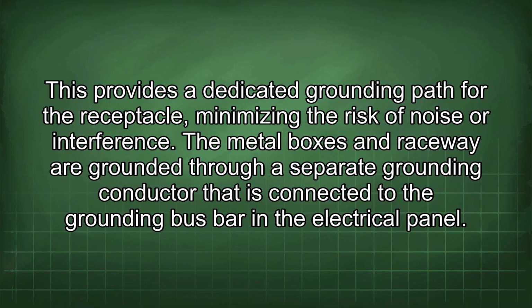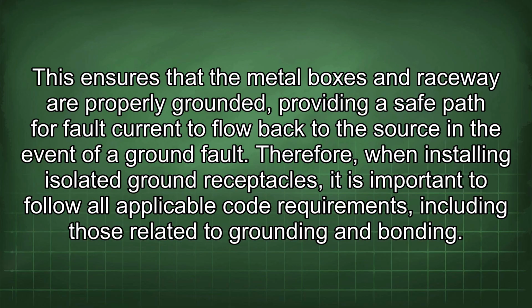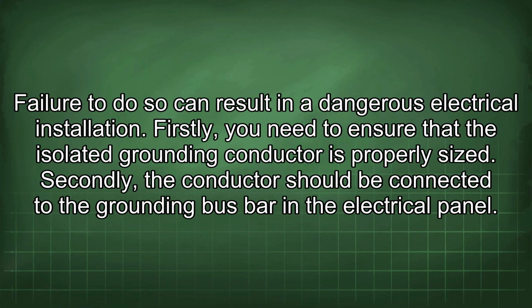The metal boxes and raceway are grounded through a separate grounding conductor that is connected to the grounding bus bar in the electrical panel. This ensures that the metal boxes and raceway are properly grounded, providing a safe path for fault current to flow back to the source in the event of a ground fault. Therefore, when installing isolated ground receptacles, it is important to follow all applicable code requirements, including those related to grounding and bonding. Failure to do so can result in a dangerous electrical installation.